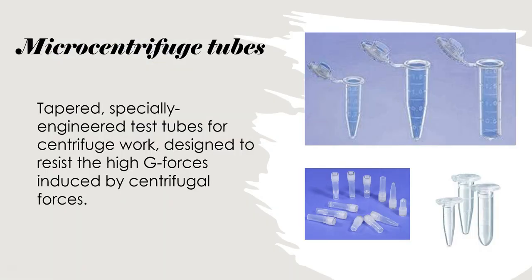To use the centrifuge, we need special tubes that will not burst or crack under the high G forces that are induced by the centrifugal forces in the microcentrifuge. These are specifically designed, usually tapered, and they usually have a little conical shape. Even when they are flat so that they can stand, there is a conical shape underneath, separate from it, to make sure that it does not crack.